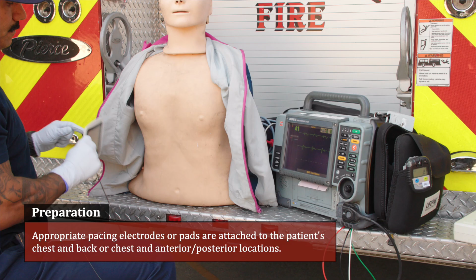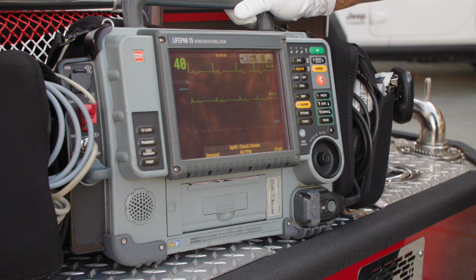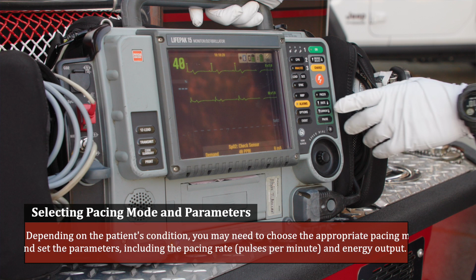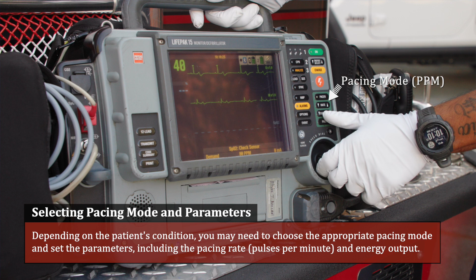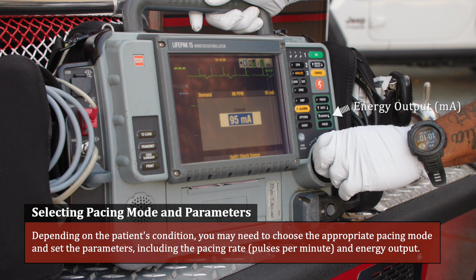Make sure the device is in pacing mode and that the appropriate pacing electrodes or pads are attached to the patient's chest and back, or chest and anterior posterior locations. Depending on the patient's condition, you may need to choose the appropriate pacing mode and set the parameters, including the pacing rate, pulses per minute, and energy output. These settings are often determined based on the patient's heart rate and the type of arrhythmia.